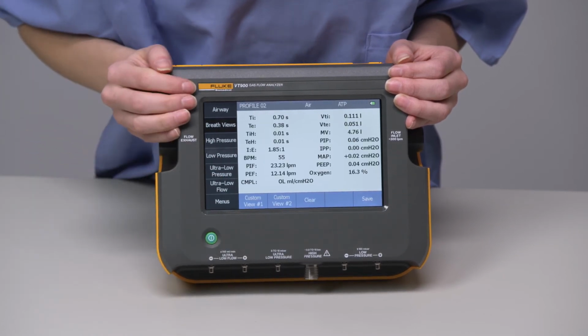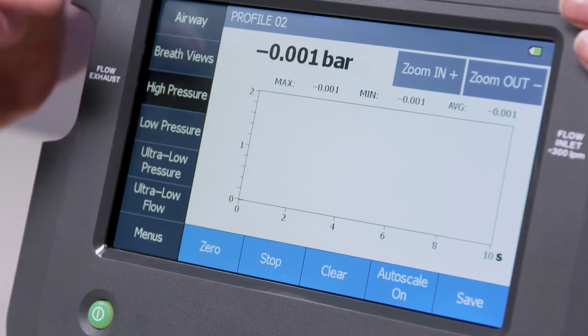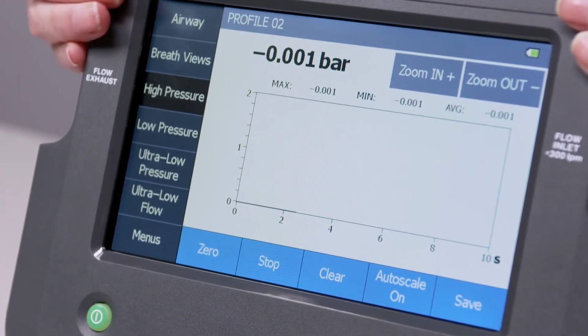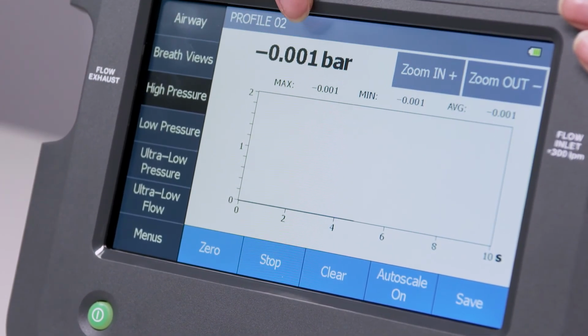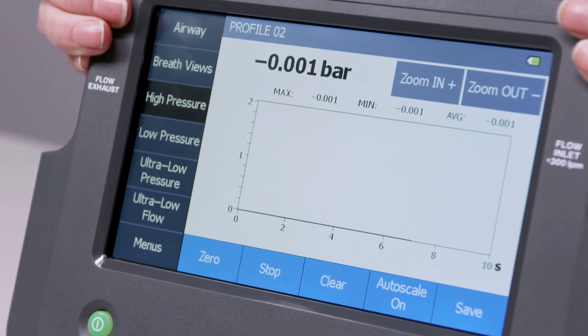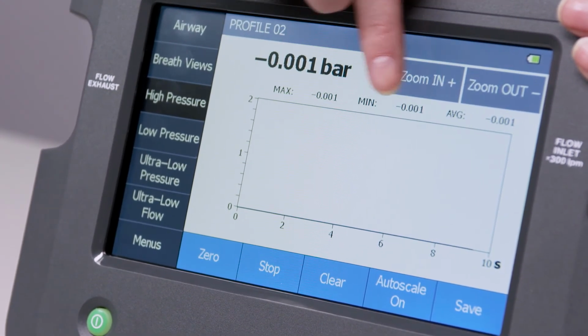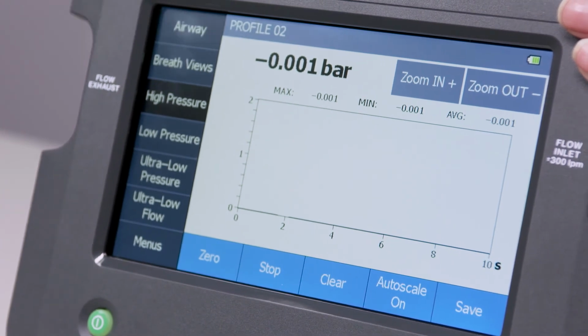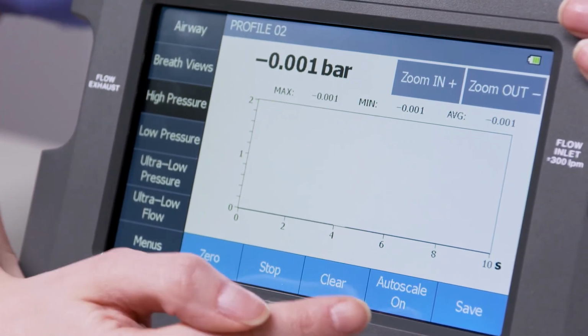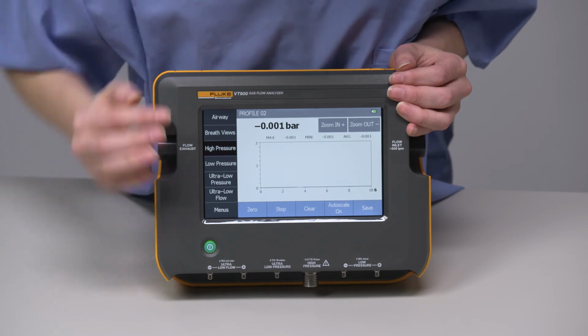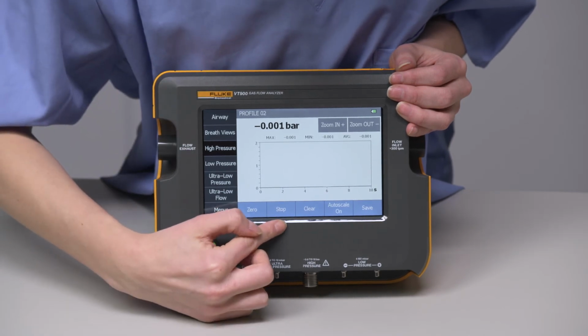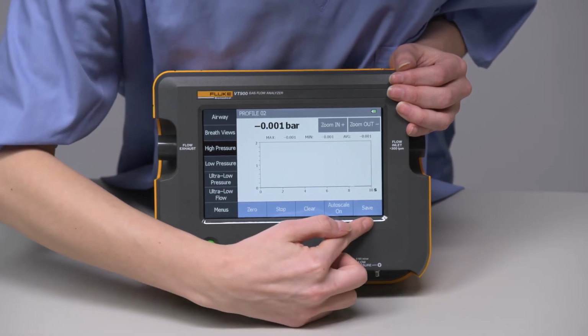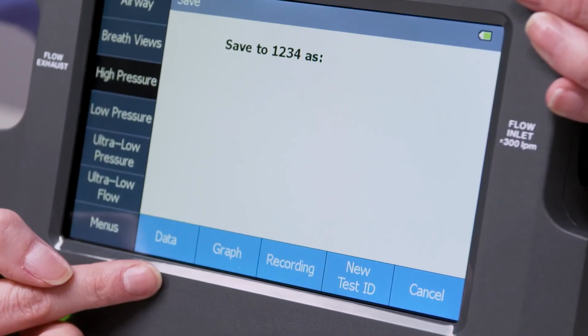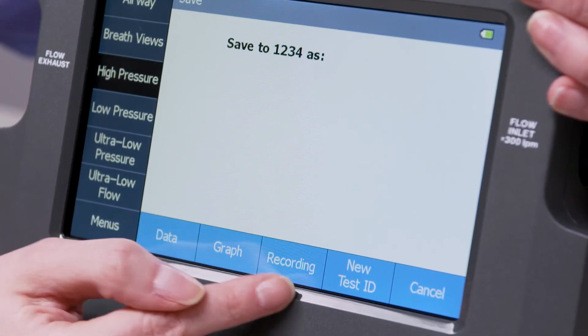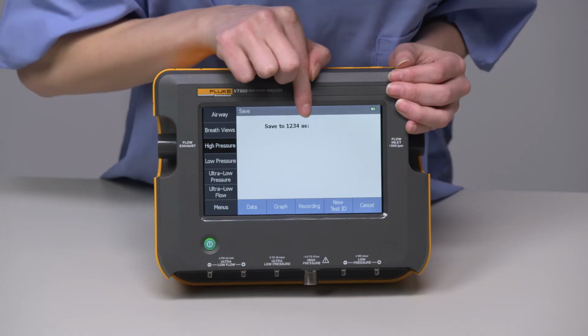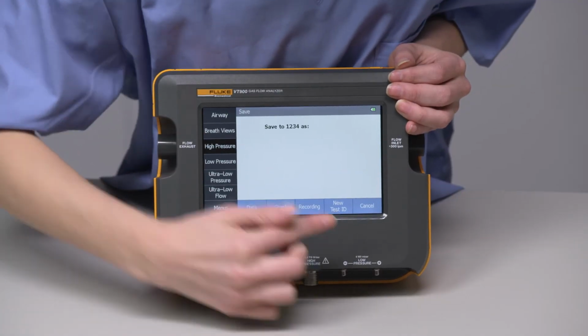Next, we have our high pressure and low pressure screens. Their layout is the same. We have a graphical reading with our real-time measurement at the top. We have maximum, minimum, and average values. We can zoom in or out, auto scale, zero, stop, clear, and save the data, graph, or recording to an existing test ID or to a new test ID.